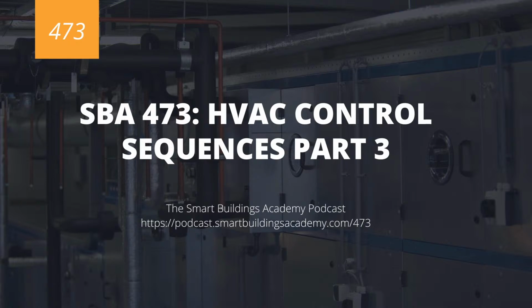So ideally, we're in the 50 to 60% relative humidity range to kind of maximize that evaporative effect. The problem is when we introduce 90% relative humidity at hot temperatures, that is a ton of moisture that has to be removed by the system.